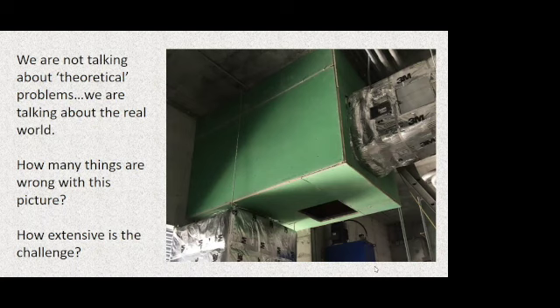Okay. The truth is, on the right, we see a 2x2 duct, which may well be okay to use steel bands at the prescribed spacing. The problem with the duct on the right is that they're using the most common joining method. Every seam has a collar around it. There's like 4 different ways they can overlap the seams correctly. And the collar method is one of them.